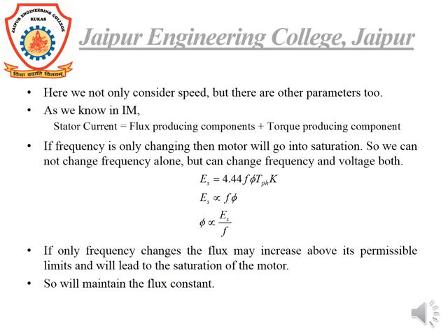Let me show you. As we know, in the induction motor, stator current equals the flux producing component plus the torque component. That's why I have mentioned that if I change the frequency only, then the motor may go into saturation. As we know, Es equals 4.44 f phi Tph K, which is the EMF equation of induction motor.